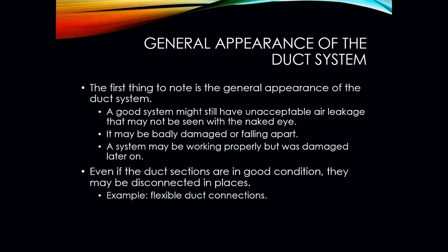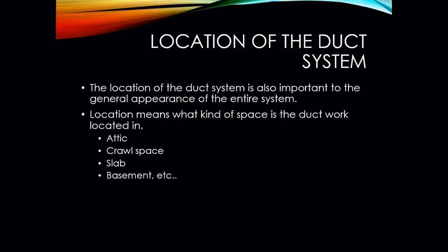A good system might still have unacceptable air leakage that may not be seen with the naked eye. It may be badly damaged or falling apart. A system may be working properly but was damaged later on. Even if the duct sections are in good condition, they may be disconnected in some places. For example, your flexible duct connections, maybe they're ripped, maybe they're torn. Look at the entire system.